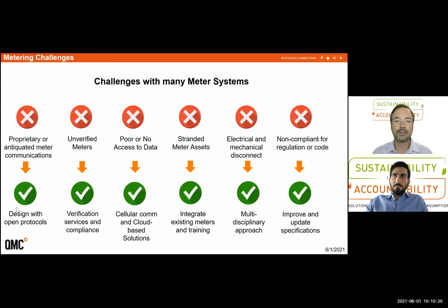A great meter can be installed, but if it's not checked that the installer installed it properly, it might be giving you erroneous reads. And actually, we find most of the time it is. So it's imperative that a meter is installed and inspected, whether that's by the manufacturer, a regulatory body, or a commissioning agent, to ensure that the system's installed properly and communicating data back properly. And typically, we look at three levels of commissioning. We want to look at the meter installation itself. We want to look at the communications from the meter to some type of data collection system. And then lastly, we want to verify that it was programmed into the software correctly, so that multipliers and other parameters are inputted correctly in the system and give accurate reads.